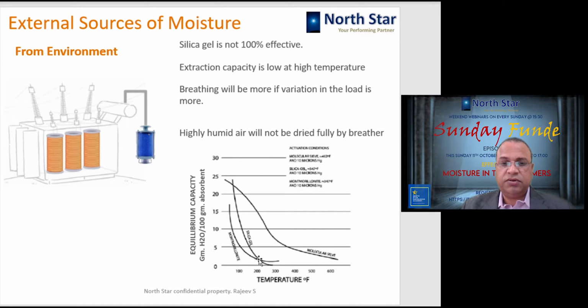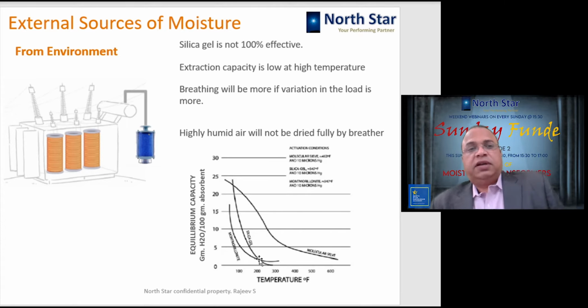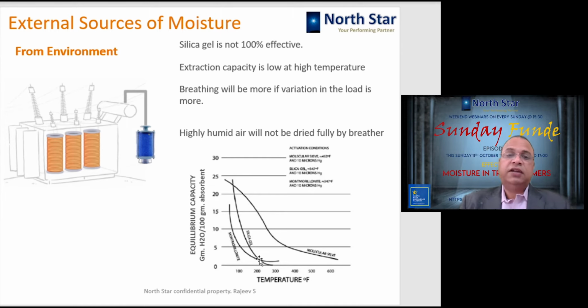If the temperature reaches around 200 degrees Fahrenheit, it can absorb only 2 grams of water per 100 grams of gel. So there is a steep drop in the moisture absorbing capacity of silica gel. Naturally, when temperatures are high and the summer is intense, especially in the northern part of the country, and also when the monsoon rains happen, the temperature is high and humidity is also high. That is a very tricky situation for the breather's effectiveness, because external moisture is high and temperature is also high, so the breather's moisture absorbing capacity is greatly reduced.